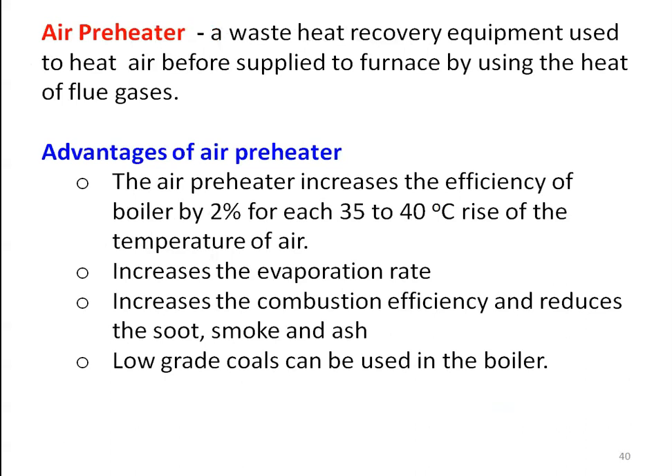The air preheater is a waste heat recovery equipment that recovers the waste heat of the flue gases to heat the air before it is supplied to the furnace. The advantages of the air preheater include: it increases the boiler efficiency by 2% for each 35 to 40 degree rise in air temperature, it increases the evaporation rate (amount of steam produced per kg of coal), it increases combustion efficiency, and it reduces soot, smoke, and ash formation.